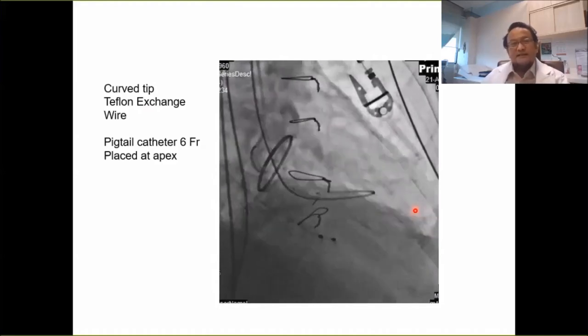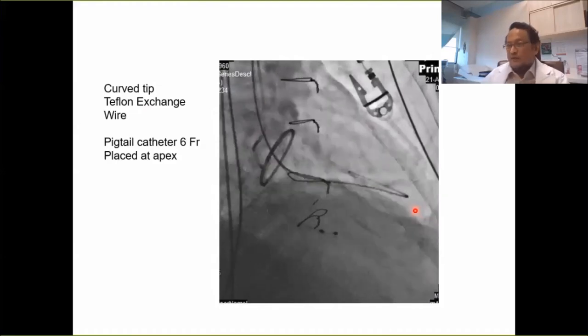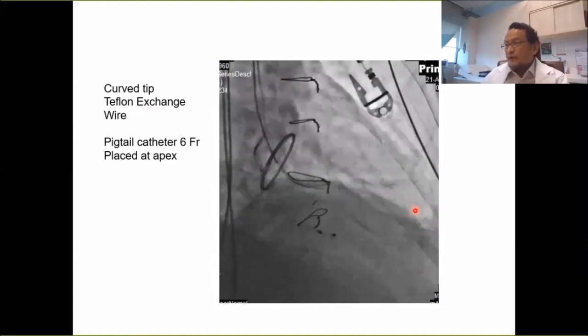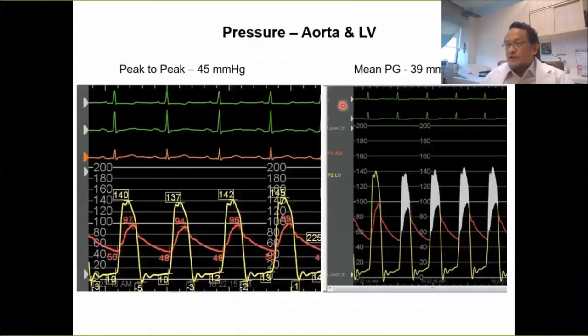This is a Confida wire supplied by Medtronic. Once the pigtail is in, we measure the peak-to-peak gradient, and you can see there's a gradient of about 45, a mean gradient of 39. That's a baseline gradient. It won't be as high as the preliminary echo, because the patient is anesthetized and under GA, which might affect the pressure gradient. It doesn't really matter anyway.